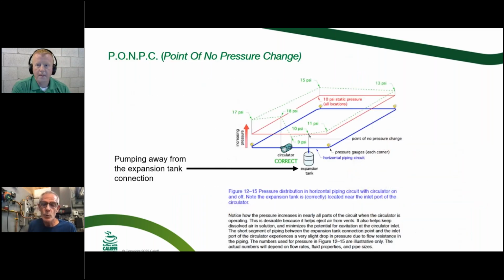Yeah, so now the person putting the system together connects the expansion tank in the system, and that establishes the point of no pressure change. We can't stretch water, we can't squeeze water, as we just talked about at these pressures. So that's the only point in that little diagram where I can't change the pressure in the system, and the circulator can't change the pressure in the system at that point.